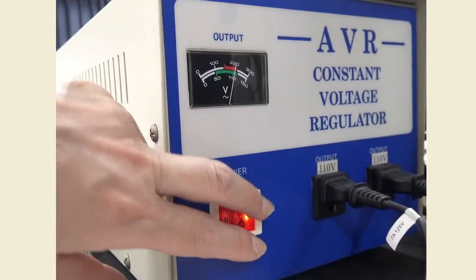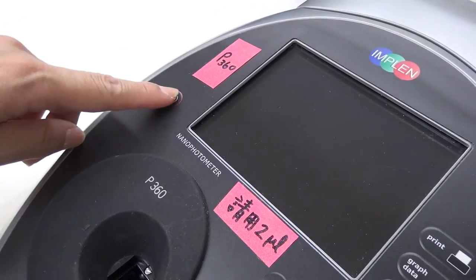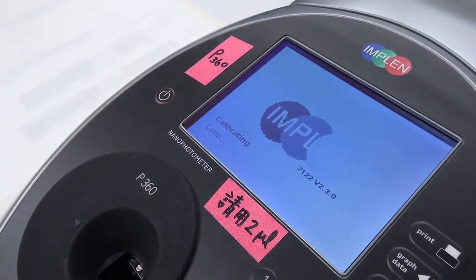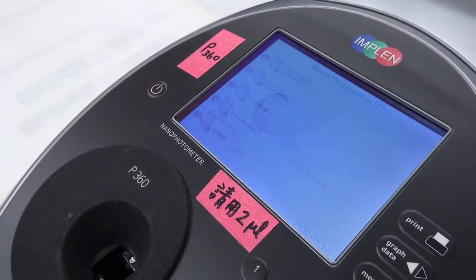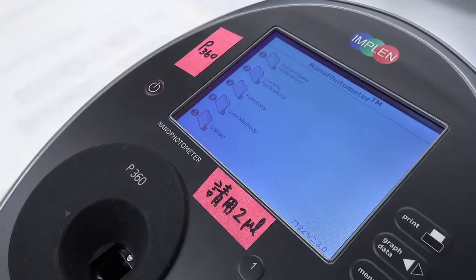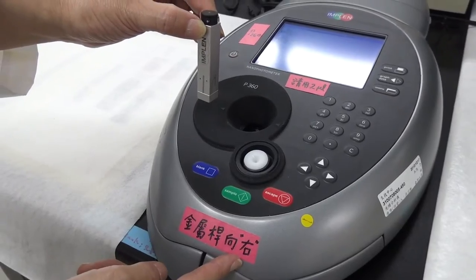2. Turn on the uninterruptible power supply UPS and switch on the spectrophotometer. The machine starts the self-test procedure automatically. 3. If the self-test completes successfully, the LCD panel displays the main menu. Put the cuvette into the holder.